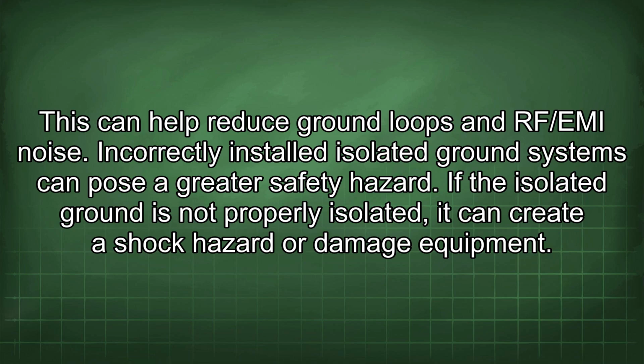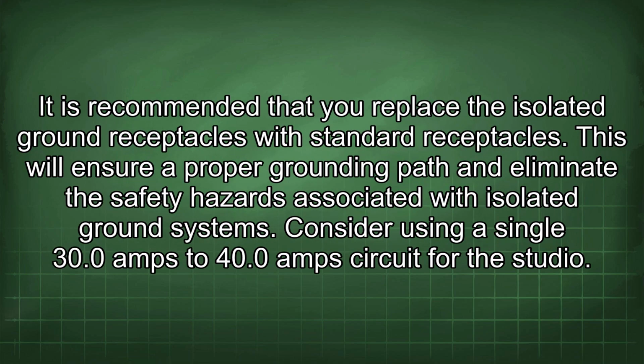Incorrectly installed isolated ground systems can pose a greater safety hazard. If the isolated ground is not properly isolated, it can create a shock hazard or damage equipment. It is recommended that you replace the isolated ground receptacles with standard receptacles. This will ensure a proper grounding path and eliminate the safety hazards associated with isolated ground systems.